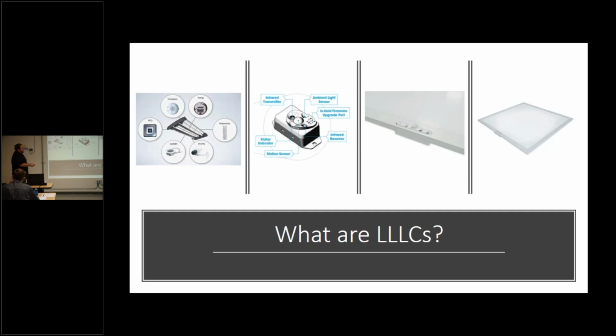And then actually placing the sensors on the fixture, it's relevant where you place them, whether it's in the corners or on the rear, and the orientation that the light is installed will affect the orientation of the data that you get. So for example, if you had a row of lights and all of them are installed on this side, and then you have 2 or 3 that are installed on the opposite side, that's something you're going to have to account for when you're collecting the data and processing it, because the distance is separate.